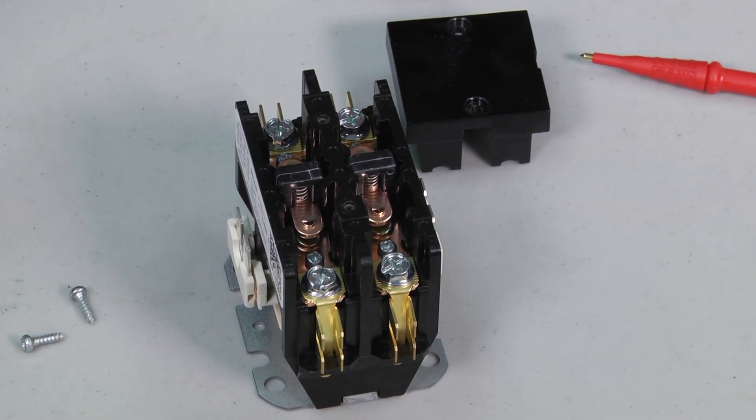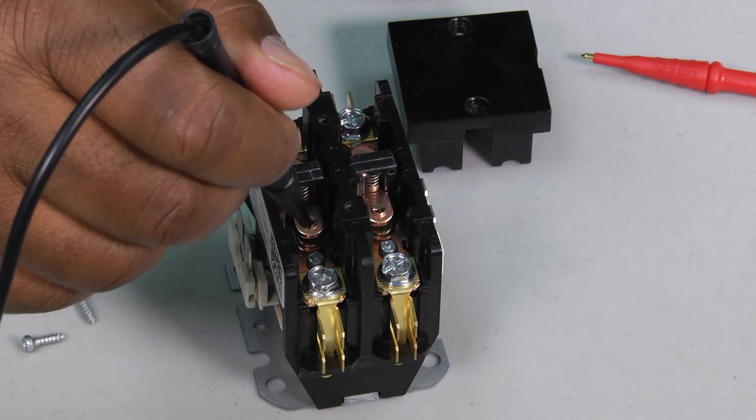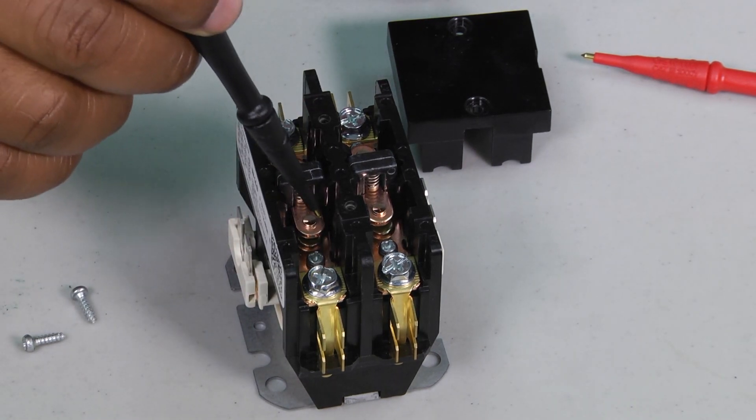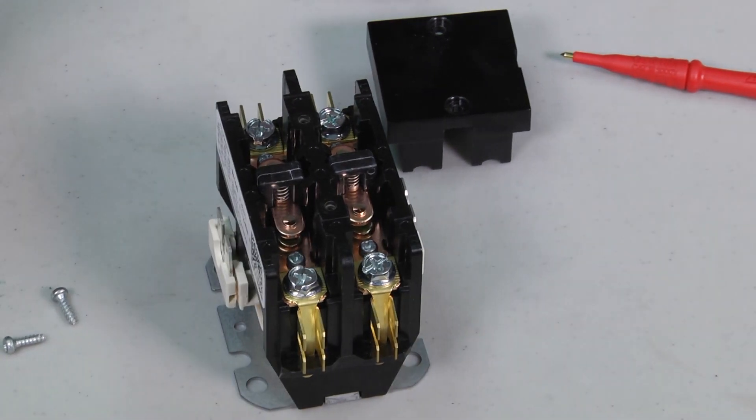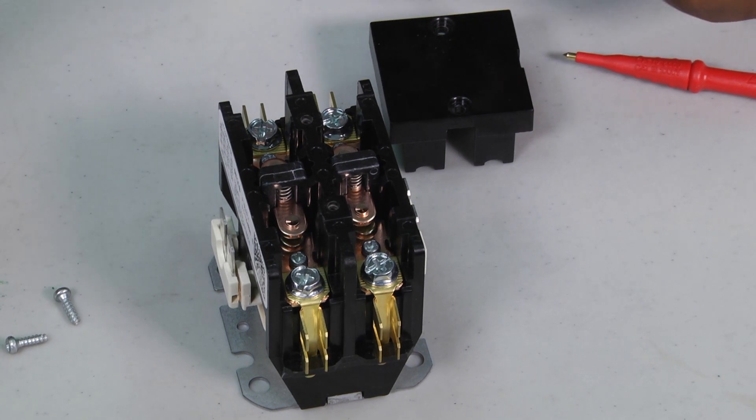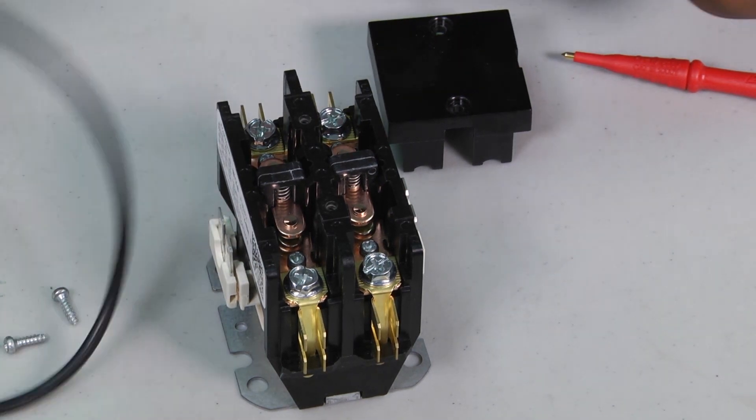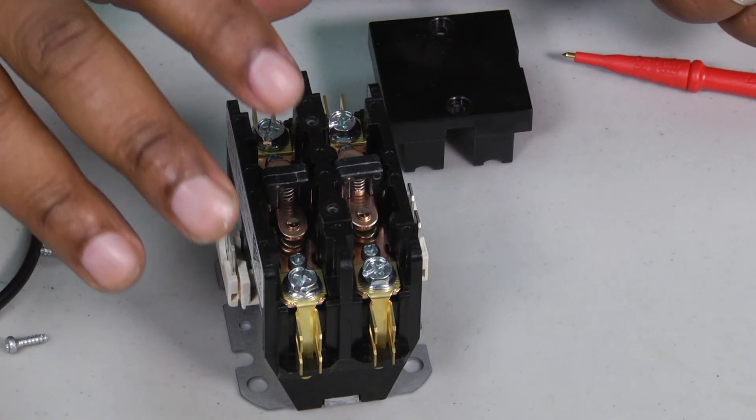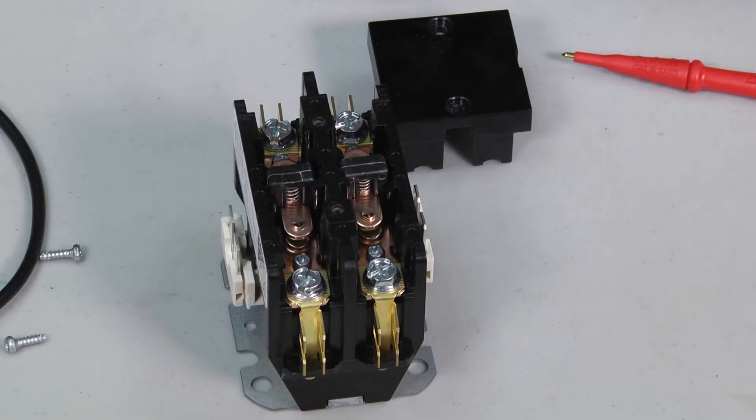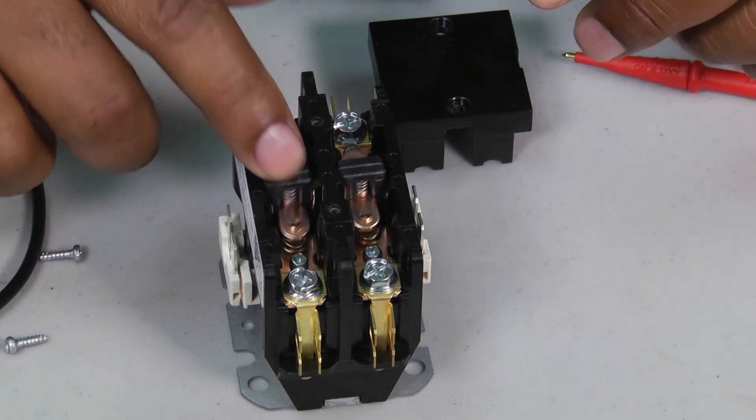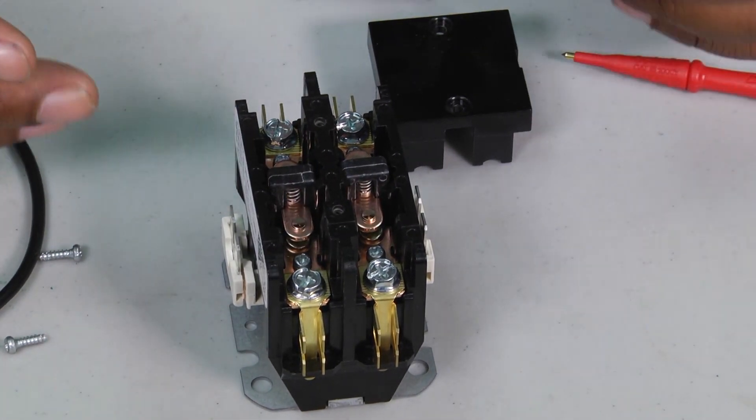Some of the common issues are on the inside, these contacts can become black or pitted from arcing. One of the things is low voltage or lack of voltage to the contactor that causes it to chatter. It'll chatter like that and happen frequently. Every time it does that, there's a little arcing that happens.